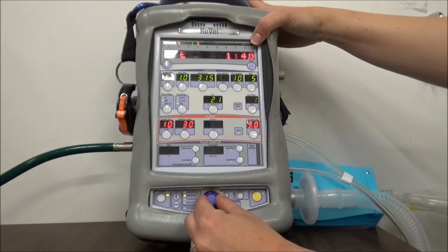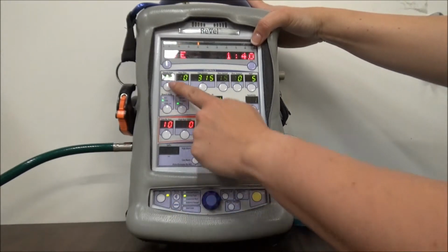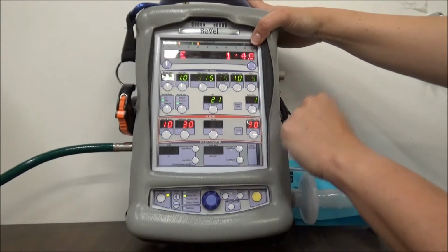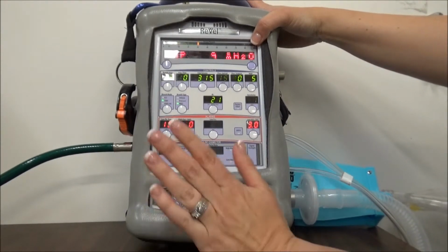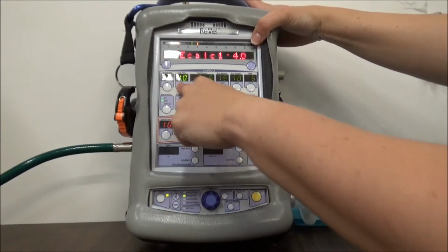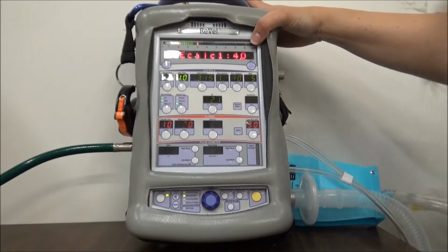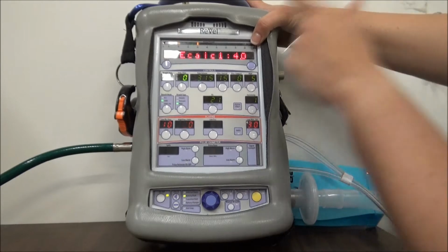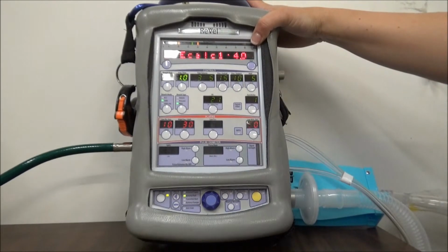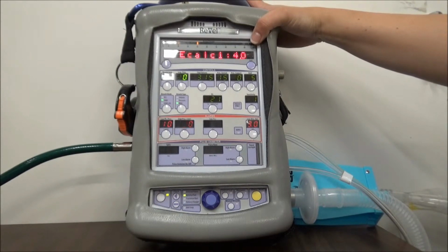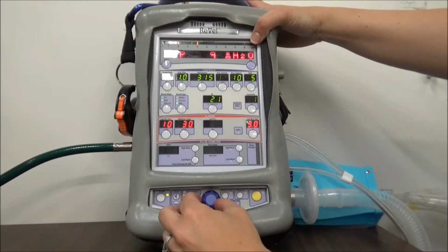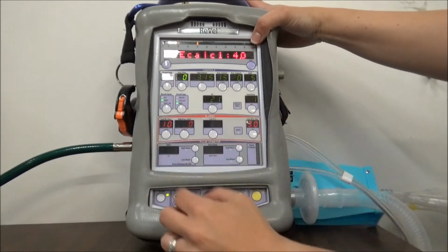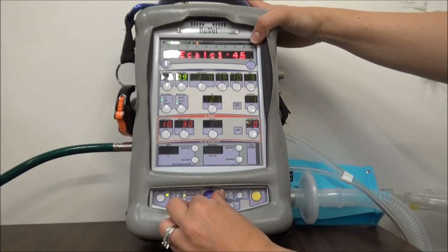There's your I/E ratio. You'll notice down here there's nowhere where we can pick our I/E ratio. It is generated off of our I time. So if you decide to do something different with your I time, as soon as you hit your I time, your calculated I/E will come up. Right now we're at a 1 to 4, which is pretty good for our obstructive patients, our COPD and asthmatic patients. If we want to make that longer, we will lower our I time.